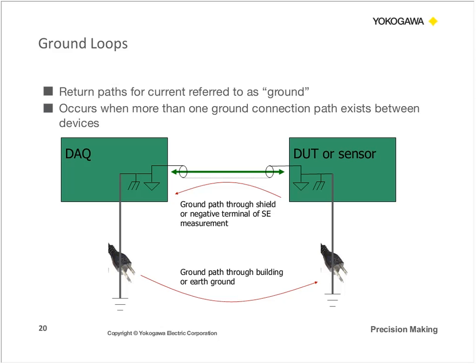So if you have instrumentation grounded in different locations throughout your facility where different ground potentials do exist, you could very well experience a ground loop if the instrument itself is not isolated, or if the device under test is not isolated from the power mains.